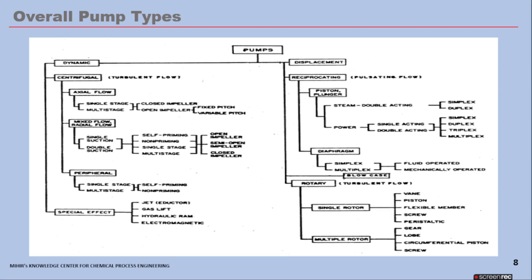The positive displacement pump operates by forcing a fixed volume of fluid from the inlet pressure section of the pump into the discharge zone, adding energy directly to a movable boundary which imparts the energy to the fluid. Kinetic pumps add energy directly to a rotating part in the form of velocity and convert that velocity to pressure. Under the kinetic category you have centrifugal pumps and regenerative pumps. Regenerative pumps are unique — the impeller is the only moving part, and they are used when high head and low flows are required. There are many types of pumps, broadly divided into dynamic and displacement types, each with a specific application area.